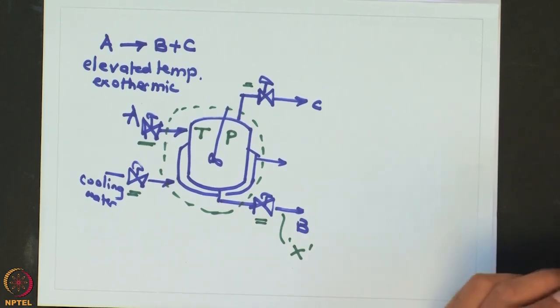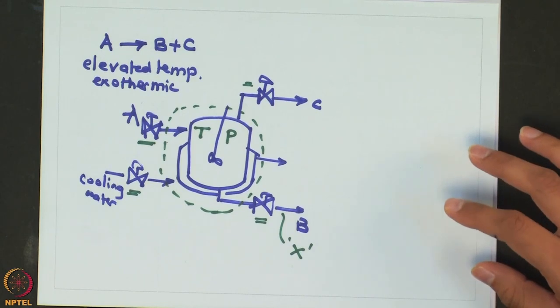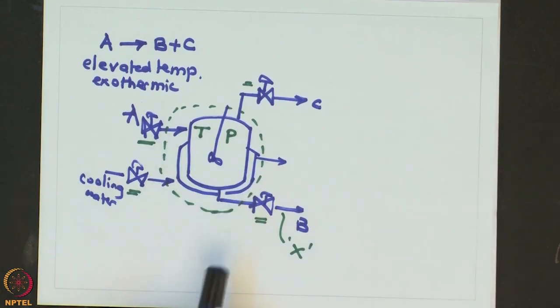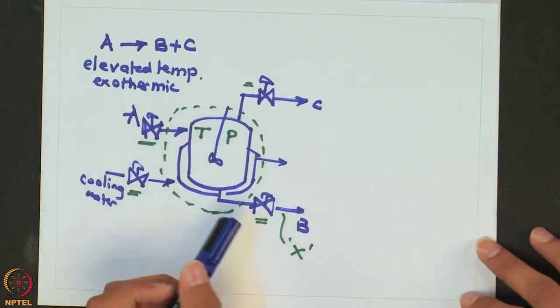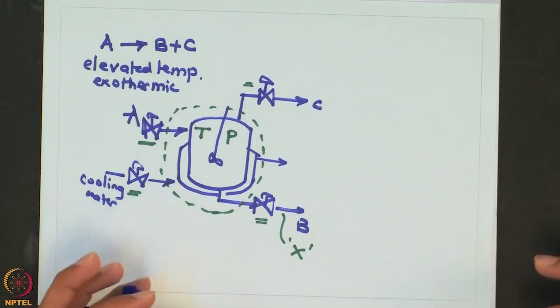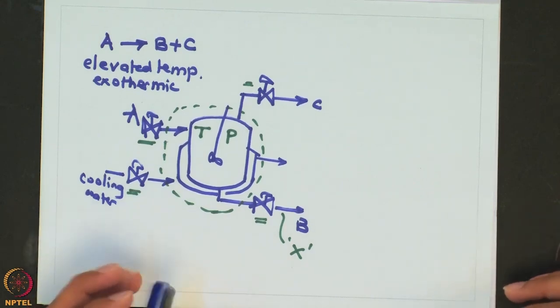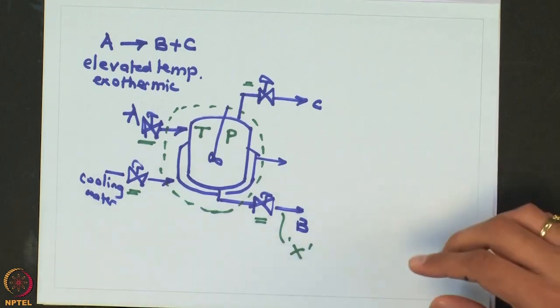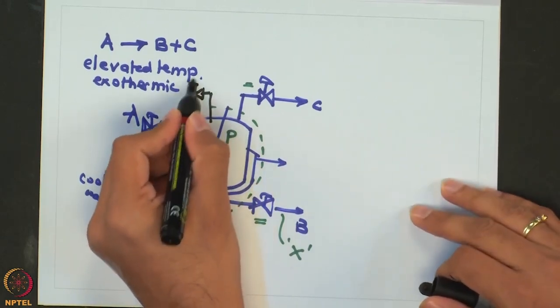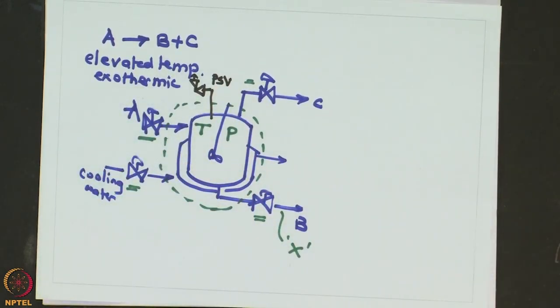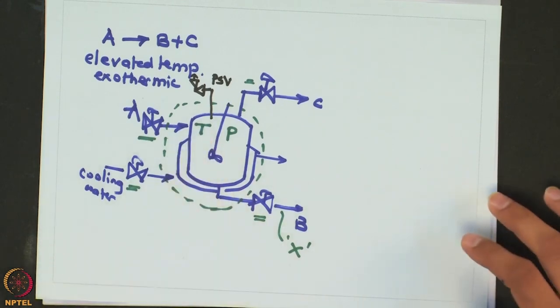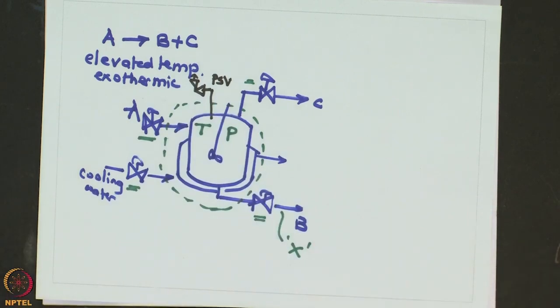The first and foremost layer is the safety control logic. In this typical example, what you would want as a safety precaution is to ensure that the pressure inside the reactor does not blow up due to unnecessary production of gaseous product C. If the pressure inside the vessel goes to a very high value, there should be a safe route — this is typically achieved by having a pressure relief valve. The pressure relief valve ensures that if the pressure reaches a very high value, it will open up and allow a safe release of the gaseous product.